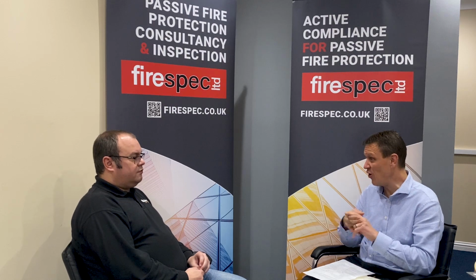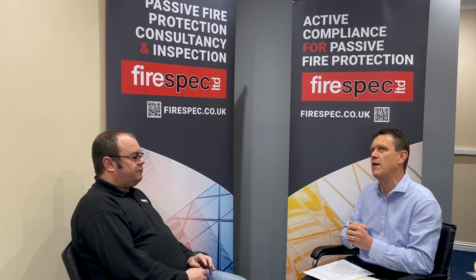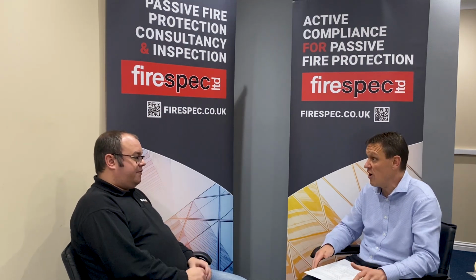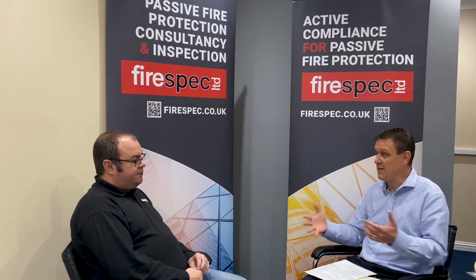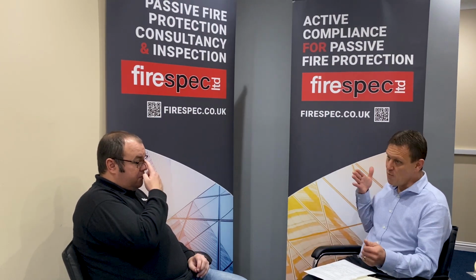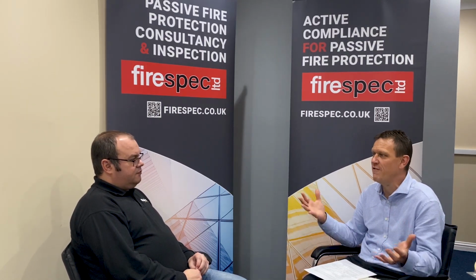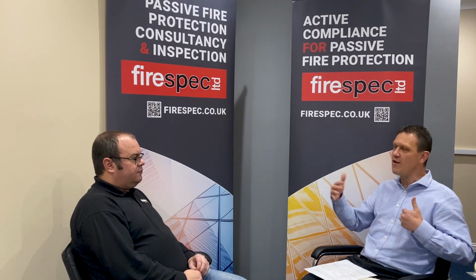So that's a problem. A lot around the refurb and that loose regulation, and then leading on to the wider problem of untested details, where it's physically not possible to test. For example, cellular beams at wall heads, or beams passing through walls. There's not a test for it. Cellular beams where there's no boxing, there's no test for cellular beams in encasement details. But where beams penetrate through a wall, you physically can't test that, because there's no loaded beam test and walls; it's a hybrid of two tests. So we can't test it. The best minds in the industry are working on it, and there's best practice and best possible solutions, but these are untested.